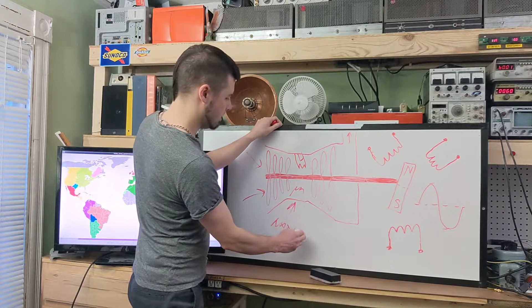The compressor uses the power grid, the power from the hydroelectric plant, to compress the air, and then when everything's up to speed, in the United States, let's just say up to 3,600 revolutions per minute, because that is 60 times 60 — 60 cycles per second times 60 seconds in 1 minute — they light the flame in the gas turbine. So they inject natural gas in here, and they fire it off with a spark.